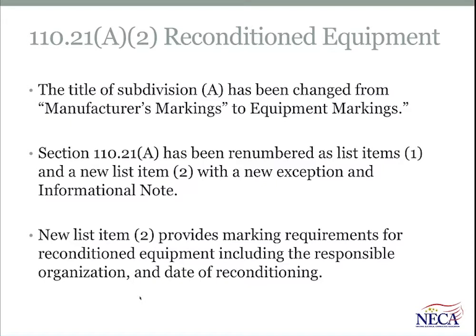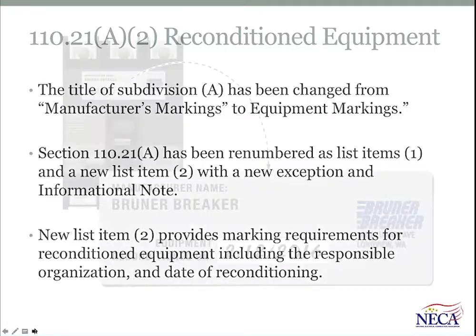This is going to be valuable for inspectors, for installers, for designers, for owners, and others who sometimes run into problems with legacy equipment where you can no longer buy new equipment to be installed in existing equipment that is energized. This is not something new. This is going on in the field. This is the code's first attempt to recognize and put requirements in place for reconditioned, refurbished, and remanufactured equipment.